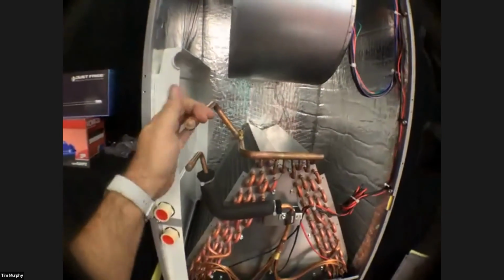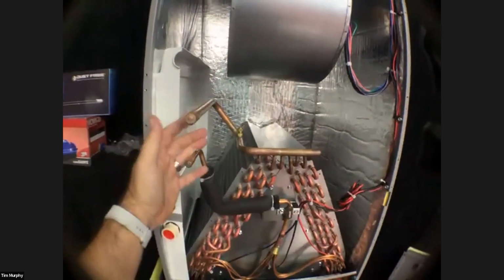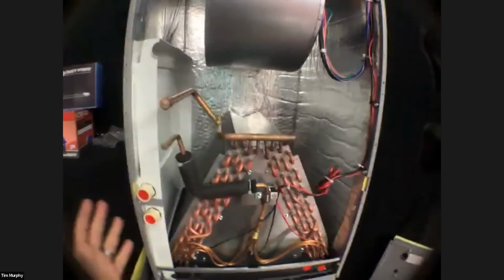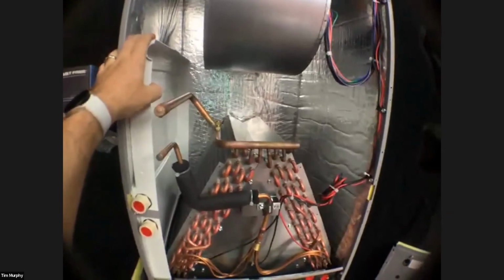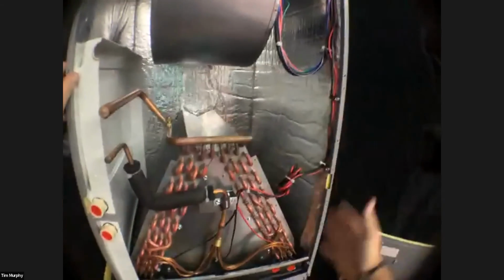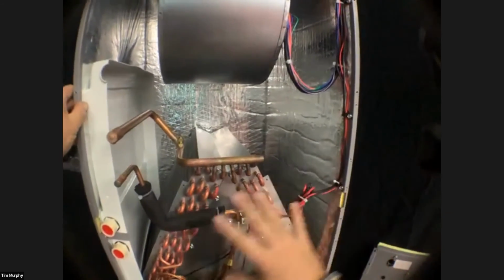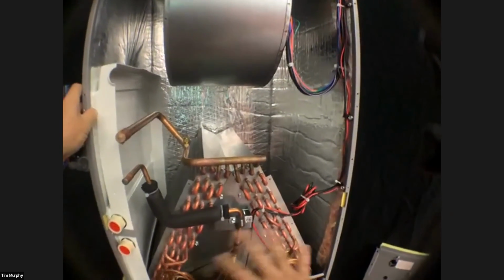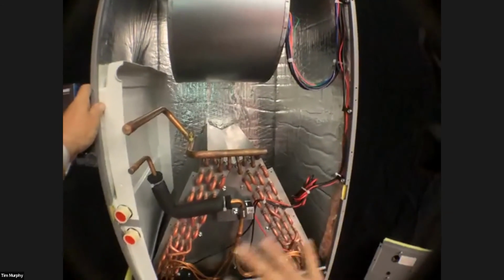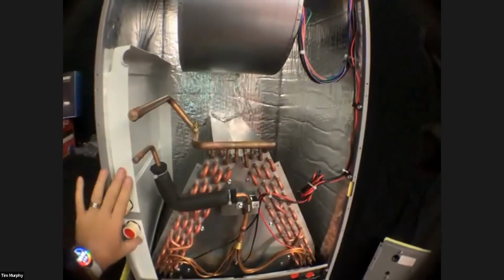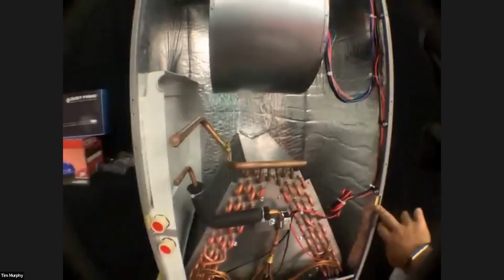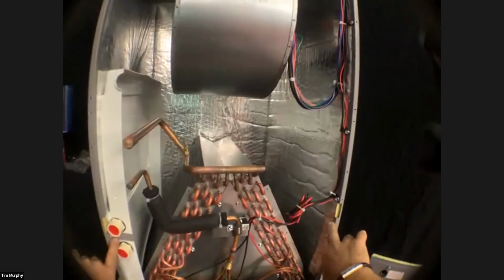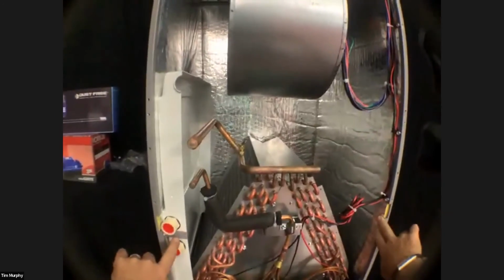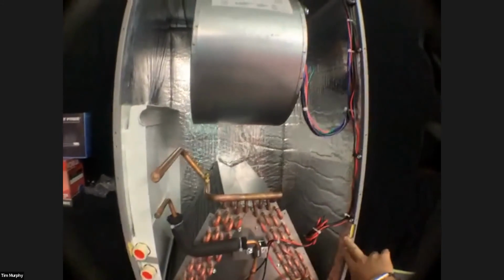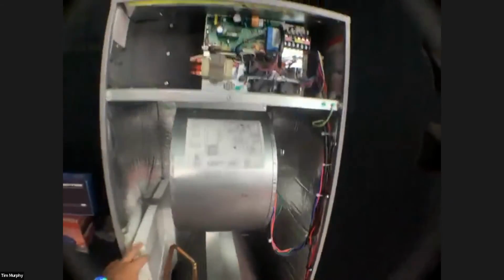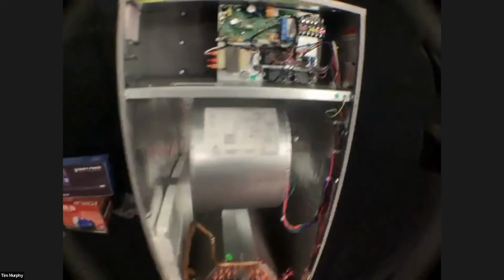Like I said before, you have the zoom lock fittings. It's going to make life a lot easier when you need to pull and clean this coil, and there's plenty of room. You've got the horizontal drain pan here, which can be flipped over and put on the right. You do not need a conversion kit to set this up in a right-hand flow, so there are no additional brackets. You just pull this out, and you can see you have preset holes here to transfer it over to the other side, and then you can set it in your right-hand application.